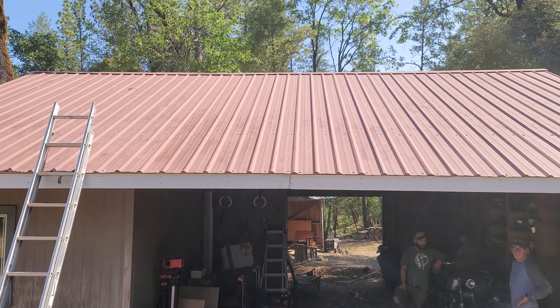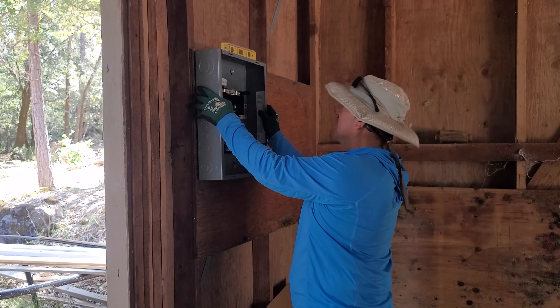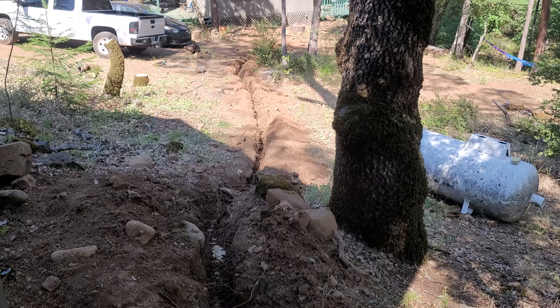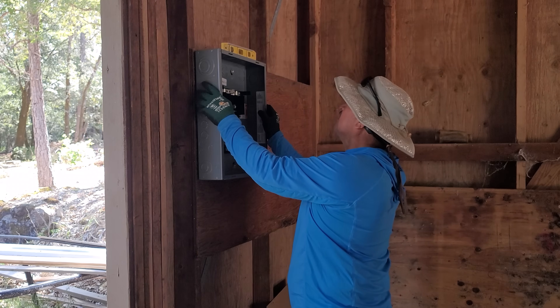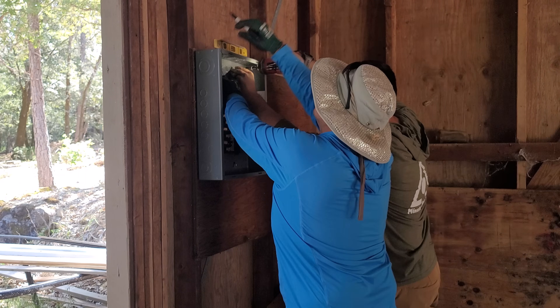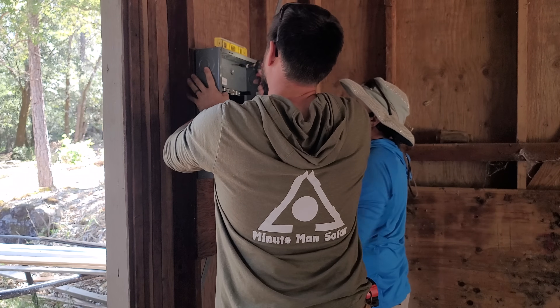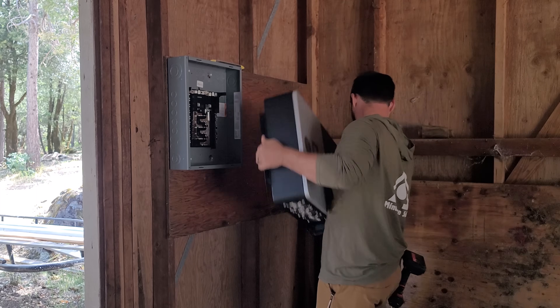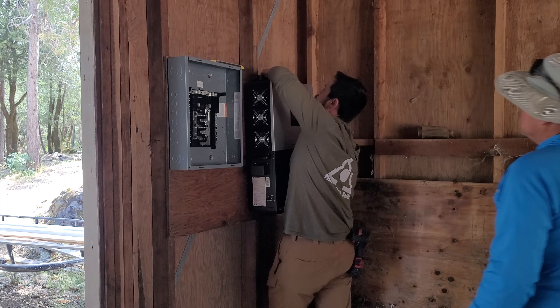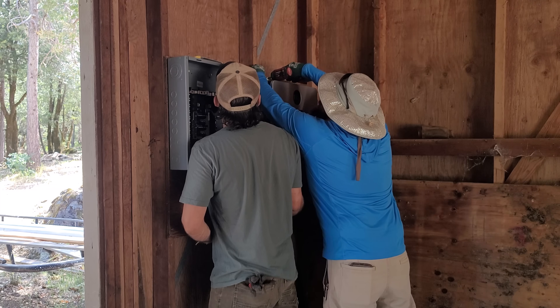They have this carport which works as a guesthouse and work area. Everything from installing a main electrical panel in the carport, digging a 175-foot trench by hand, and pulling wire that was extremely difficult — we're going to go through this installation step-by-step. They've chosen the 6000 XP off-grid inverter from EG4. It's a very reliable option and one I usually recommend — it's even the one I use to run my own off-grid cabin. We'll be wiring this main electrical panel to the inverter to supply power to both the guesthouse and the main house. Your main electrical panel needs to be grounded.